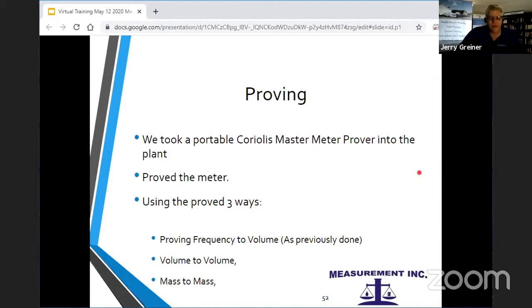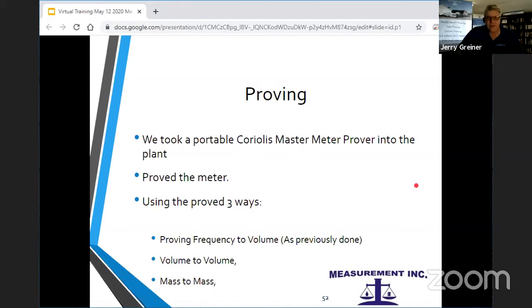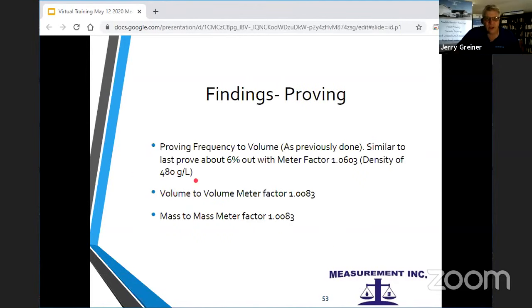We took our portable in and we proved it three different ways. We proved it frequency to volume, the same as the bidirectional ball prover had been doing. Then we proved it volume to volume, and we also proved it mass to mass. And what we found is when we proved frequency to volume, as it was previously done, we got basically a similar K factor to what the ball prover had, the 1.06 number. Our density was 480 grams per liter. When we proved it volume to volume or mass to mass, we got the same meter factor of 1.0083. So mass to mass and volume to volume were the same, but frequency to volume was quite different.